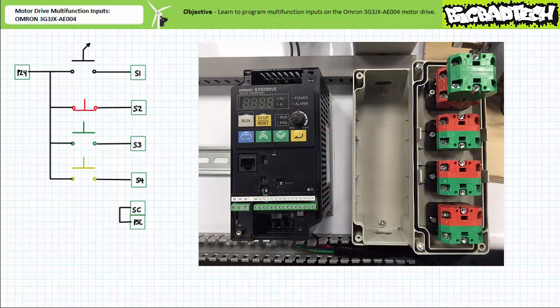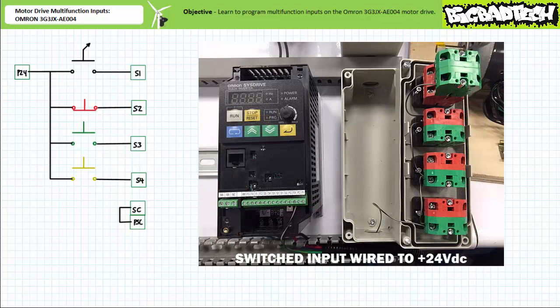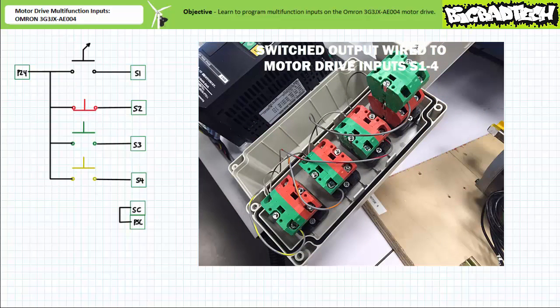Let's wire them up top to bottom: normally open selector switch, normally closed red push button, normally open green push button, normally open yellow push button. Make sure you can positively identify the switch and the terminals. Despite the fact that the push button enclosure is right next door, realize the purpose of this exercise is to remotely control this drive from a different location — this push button enclosure could be in a different room, building, state, country, or on a different planet, provided you had wires that long.